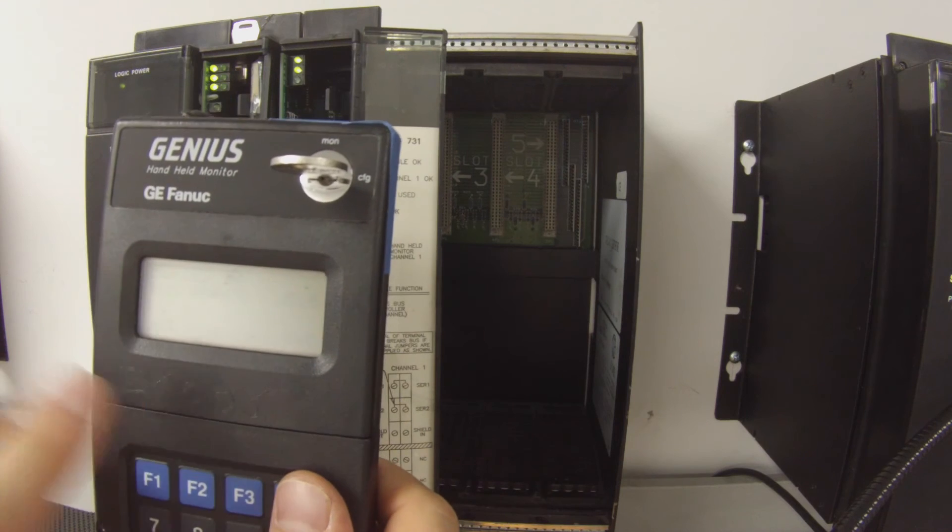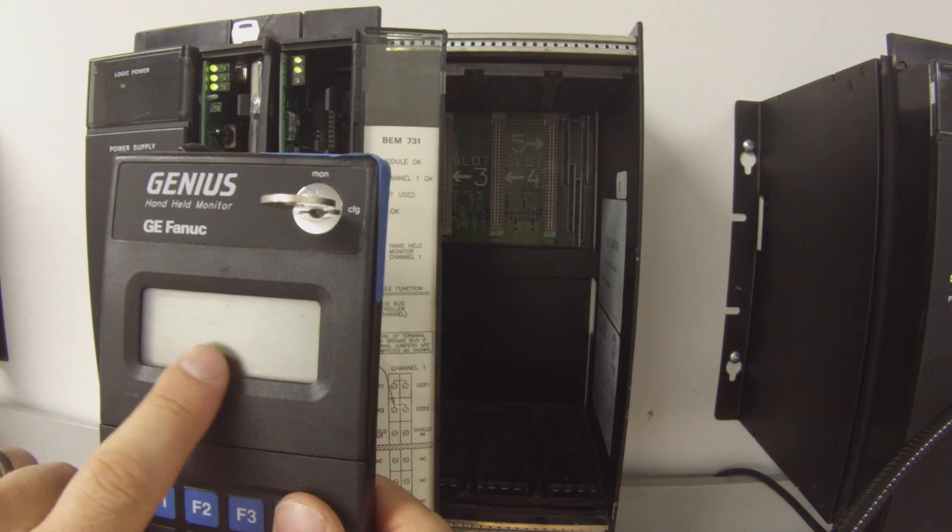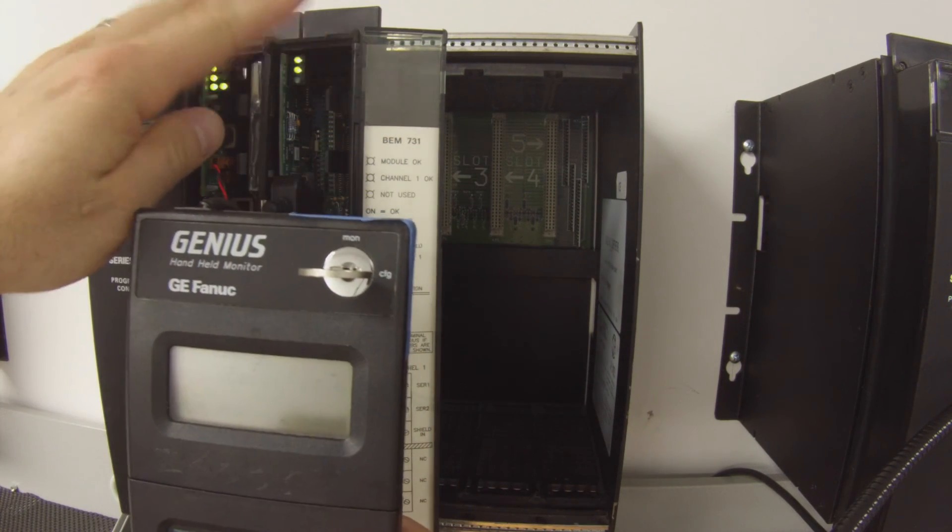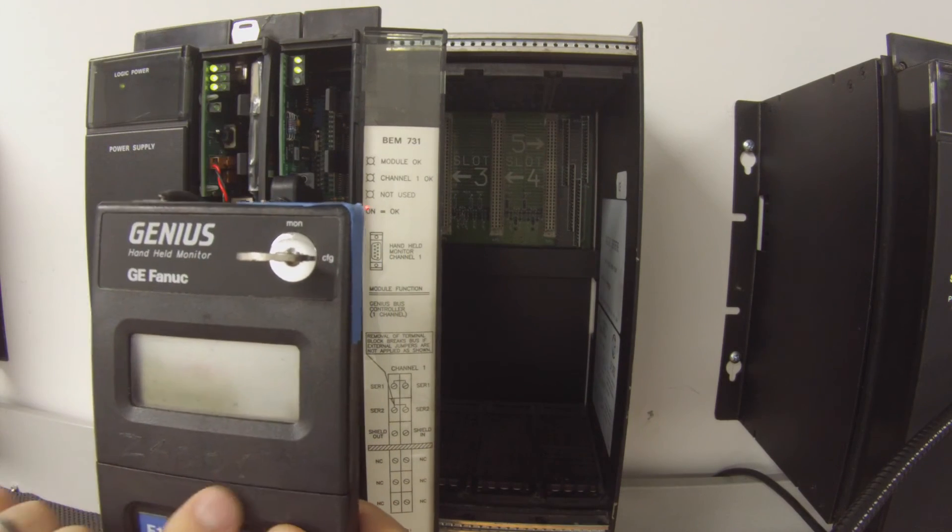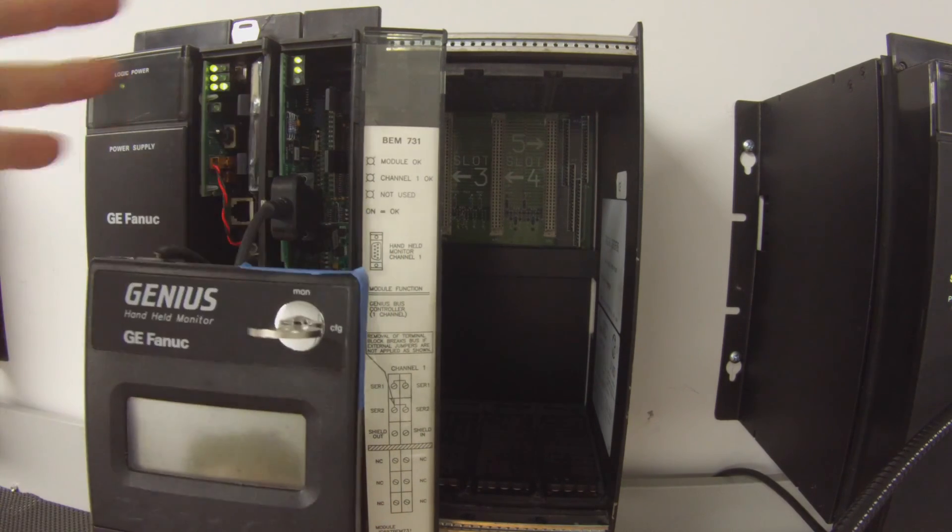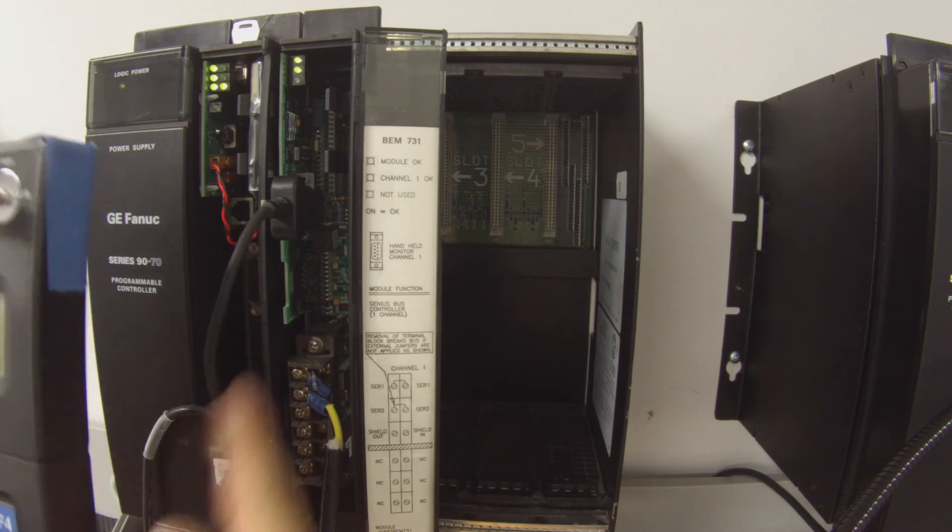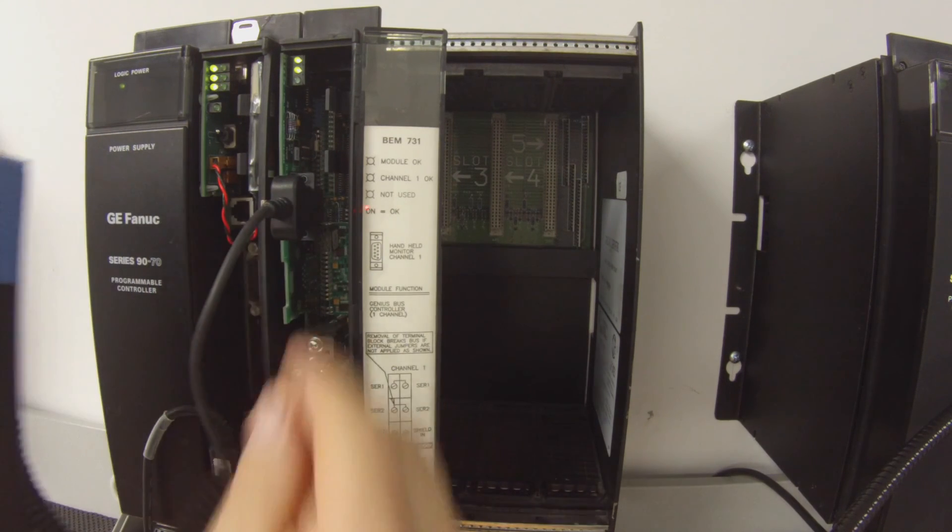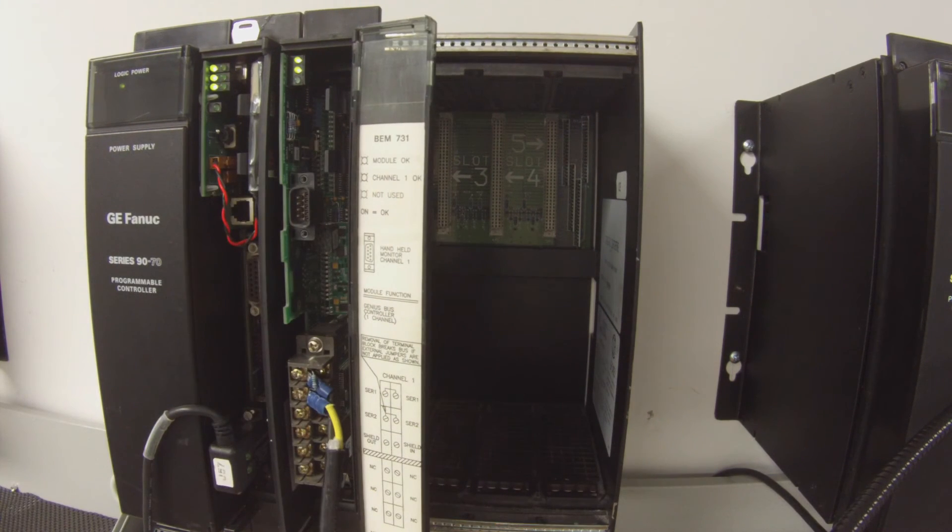OK, so now I have bus address 31, which is the device we have here, version 5.5. This is telling me that this is a communicating working device. That's how I know, all right, that this port is working. So now we've tested both ports.